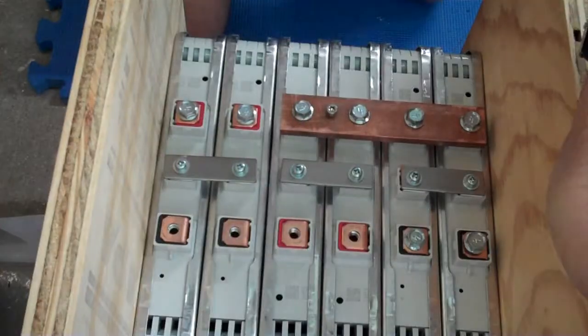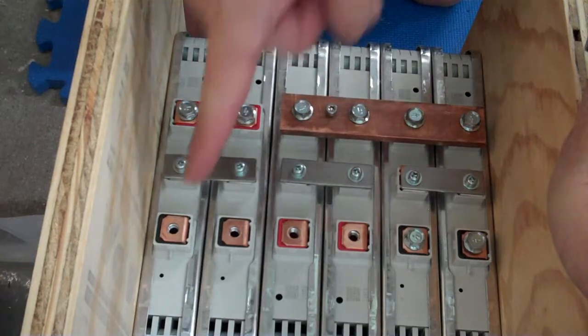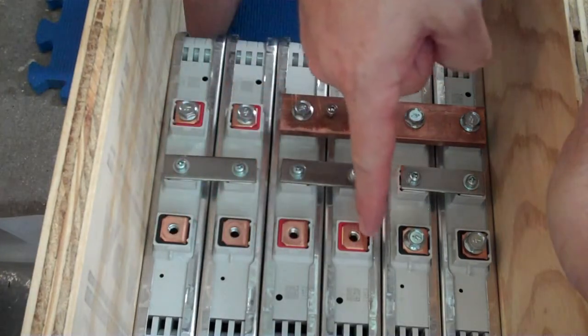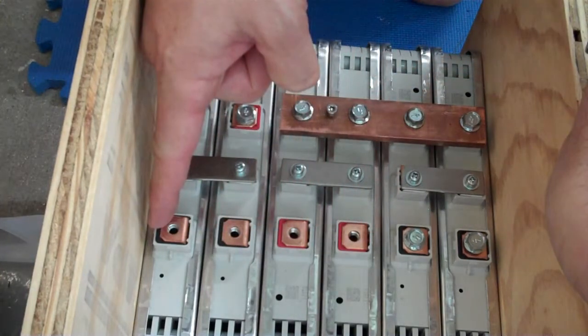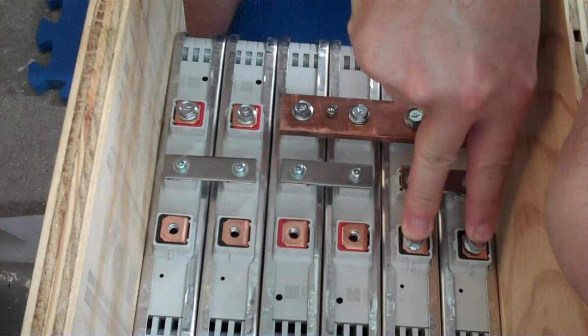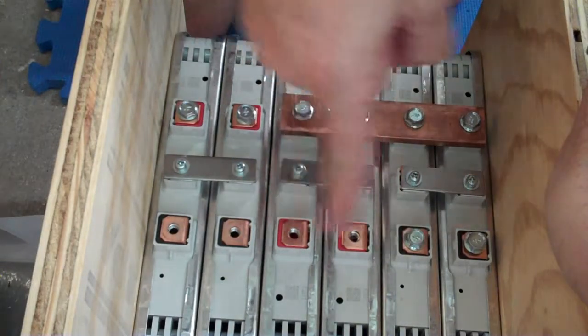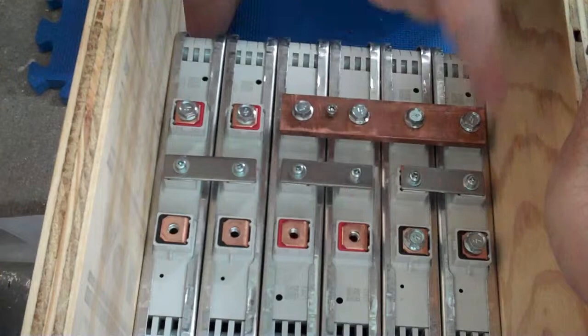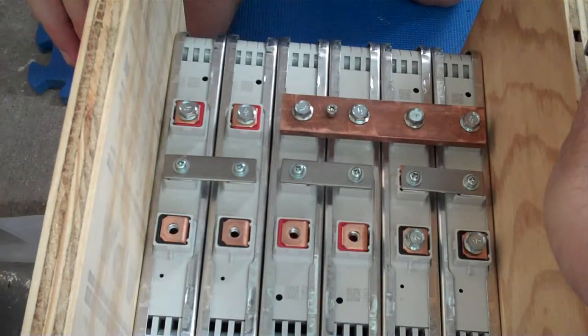You need to be careful when installing your bus bars. Think twice and connect once. I removed only the four bolts that are the correct location as a reminder that if I were to place this bus bar in the wrong spot, it could short out four modules and cause excitement.